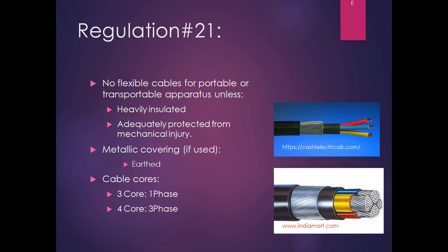That's why their cables should be heavily protected from the mechanical injury, as well as they should be protected against electrical faults also. If metallic coverings are used, metallic covering means either you can use arming or somebody uses flexible conduits. The metallic covering shall be earthed. We used to earth the arming part of the cable, and if conduit is used, that has to be earthed also.